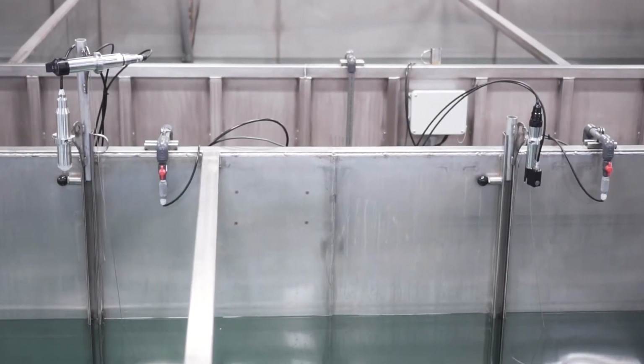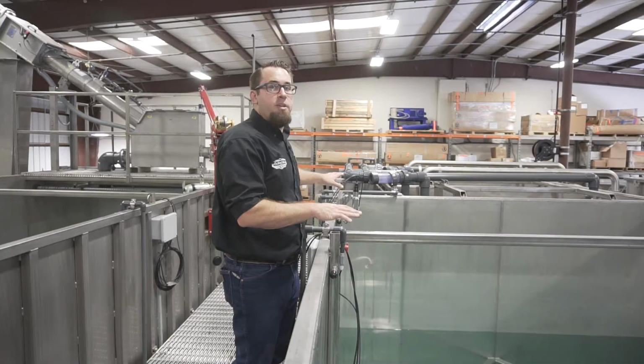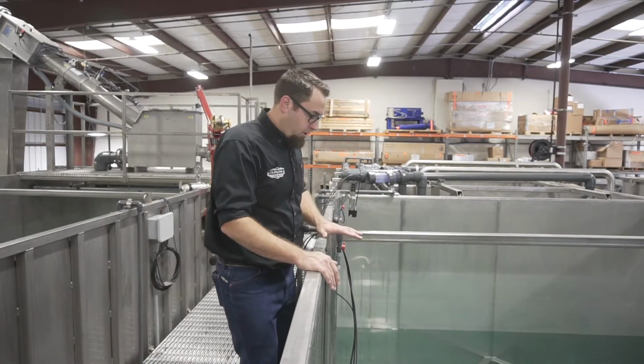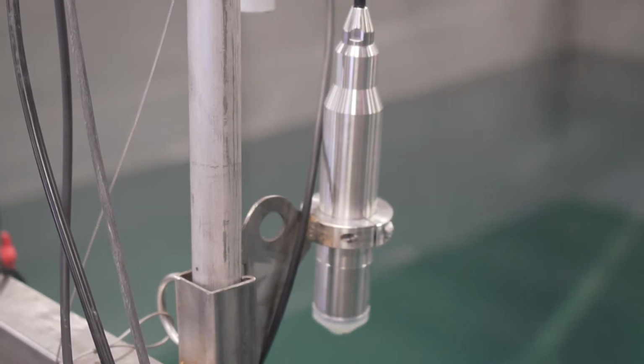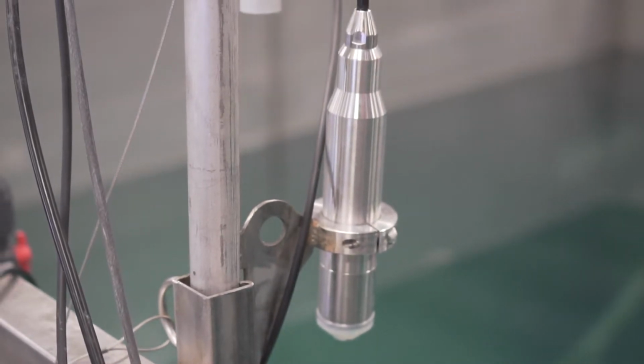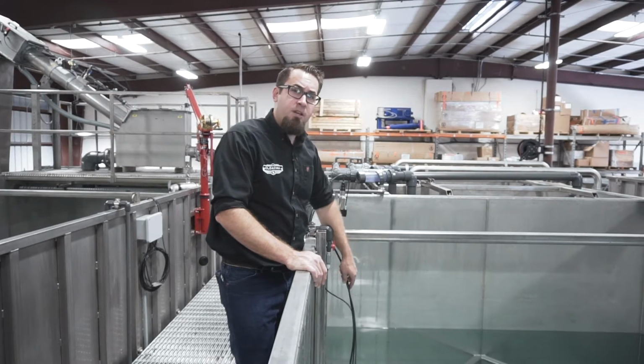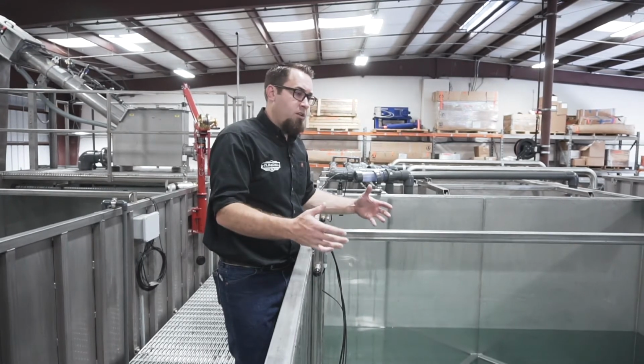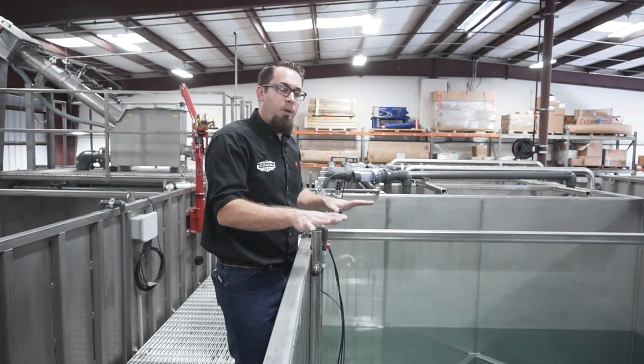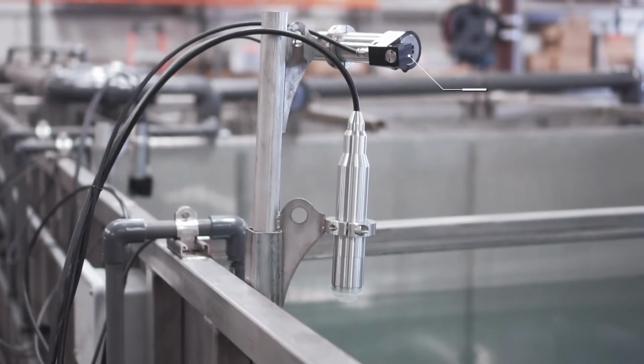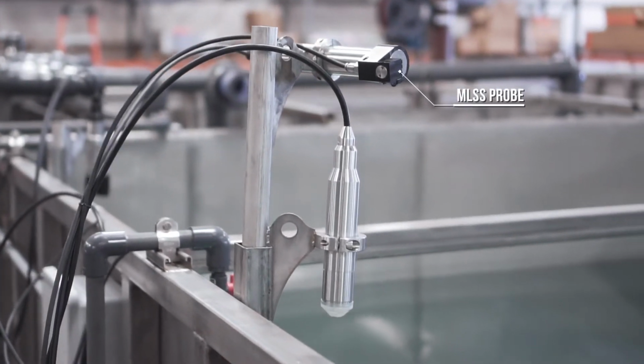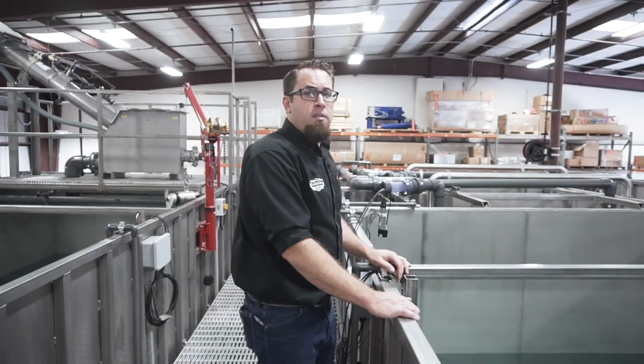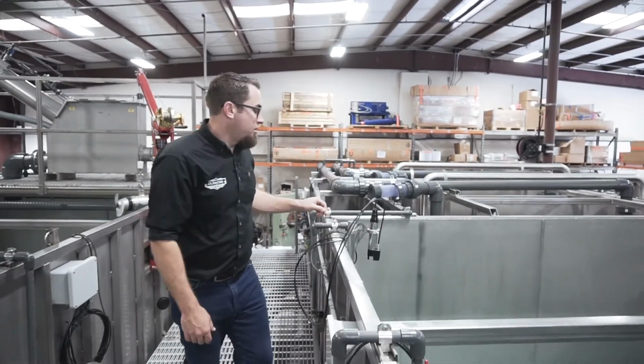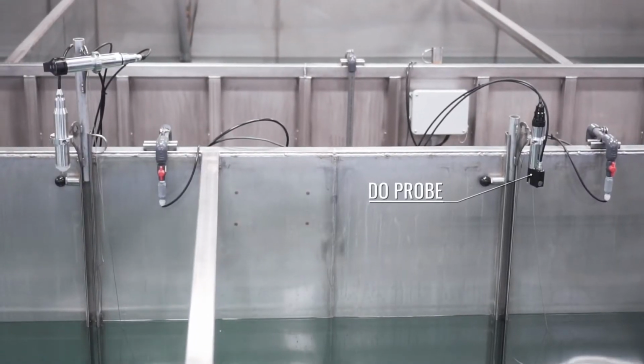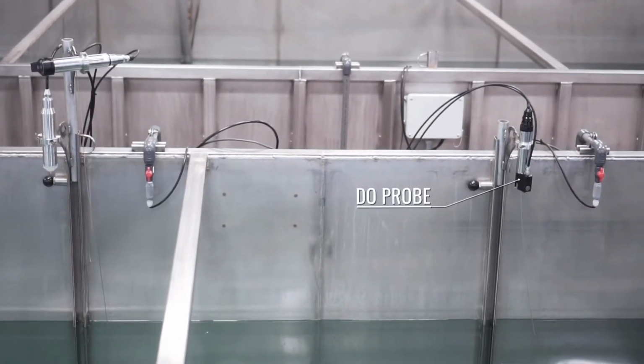In front of me, you'll notice two slide rails that have three pieces of sensory equipment. The first one is the level transducer, which is set to the bottom of the tank. The second one is the mixed liquor suspended solids probe, which allows us to run a program so that we can automatically tune and adjust the wasting based off of the actual mixed liquor suspended solids in the aerobic zone. The next one is the dissolved oxygen sensor. This allows us to actually fine-tune the aerobic set points to your specific project needs.